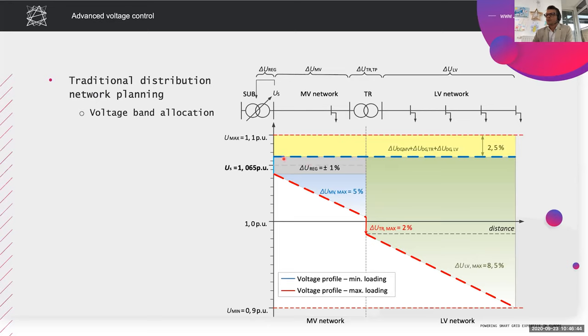One of the worst operating conditions is also that the load is zero. This means this is the upper curve, the blue one. So the blue curve I'm showing here on the graph. If there is no load in the network, then the voltage at the customer connection point will be more or less the same as the voltage here at the transformer. And you have only this space, so 2.5%, allowed for the connection of distributed generation. So this is the voltage increase which is allowed in this network in order not to break the upper limit, which is set at 1.1 per unit or 10% above the nominal value. So this is a fairly simple approach.